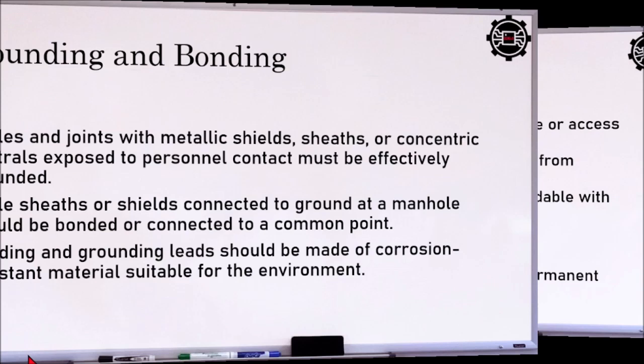So ito sa bonding, dapat all of our cable that are connected to ground must also be bonded to the cover of the manhole, especially if the cover of the manhole is metal. Then bonding and grounding leads should be made of corrosion-resistant material suitable for the environment. So yung ating mga gagamitin as the bonding or the grounding lead should be corrosion-resistant. So hindi siya tinatabla ng kalawang.